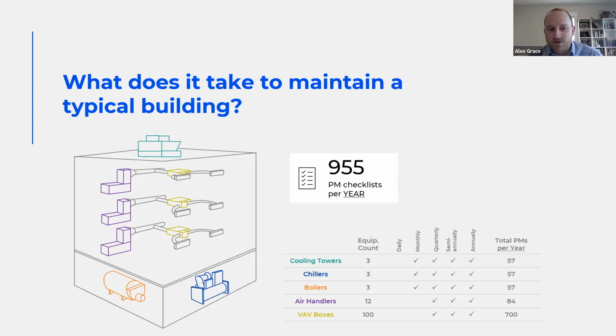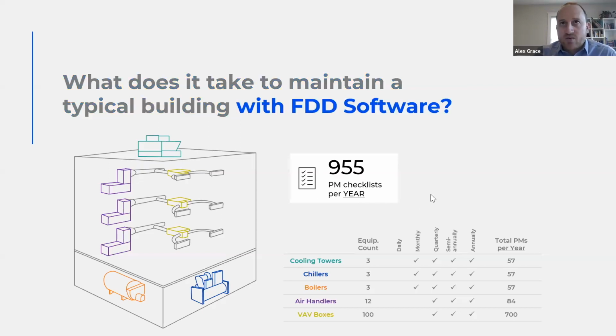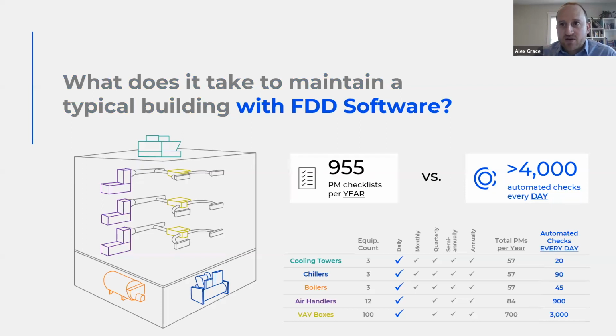We know that reactive maintenance is the most expensive form of maintenance, and that's the value of being proactive. So what does this look like with building analytics, with fault detection and diagnostics running? When you have FDD software in the picture, it means you now have automated checks running on each piece of equipment every day. In this example, we're looking at about 4,000 automated checks every day, as opposed to about 1,000 checklist items per year.